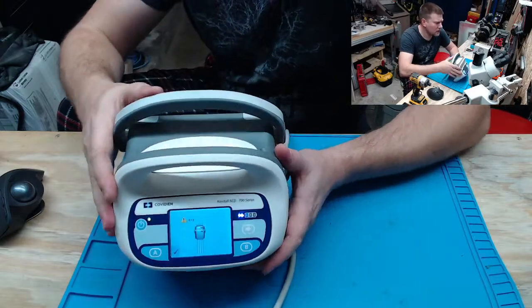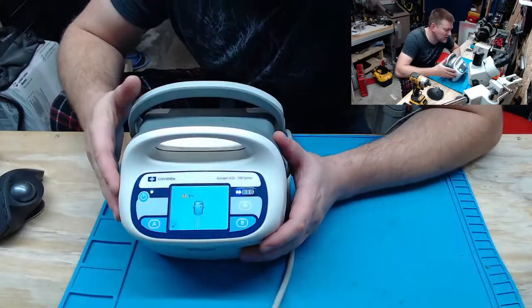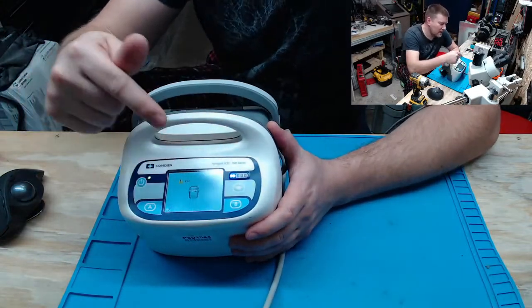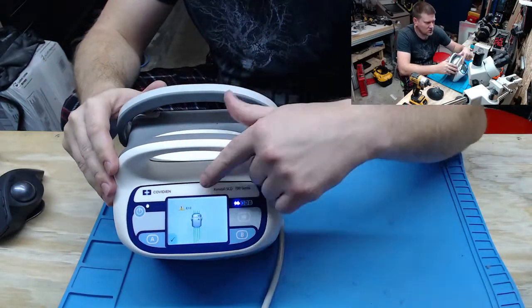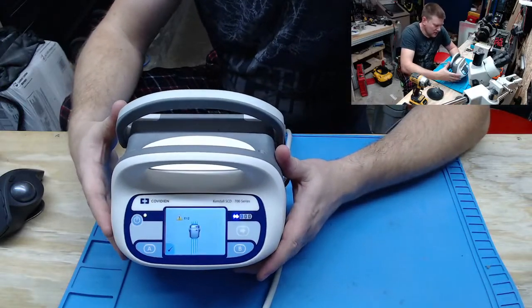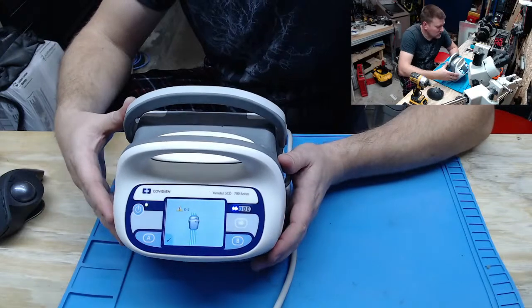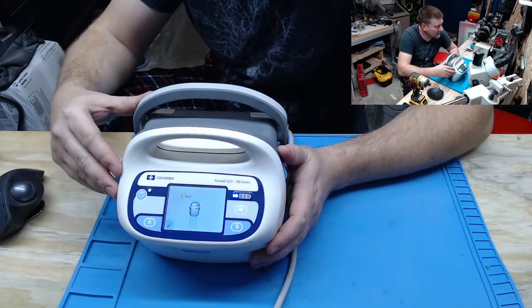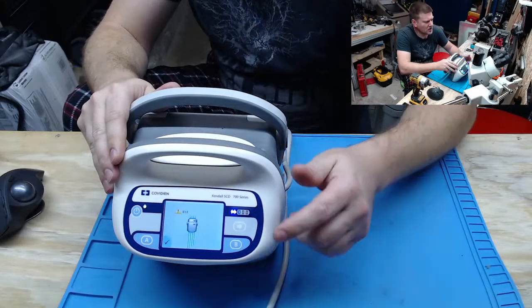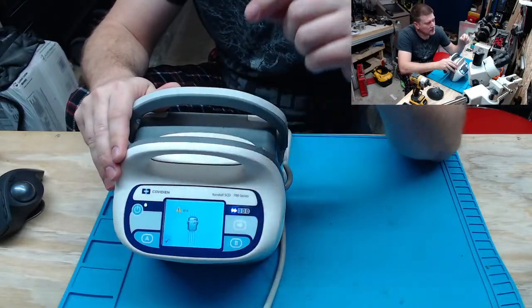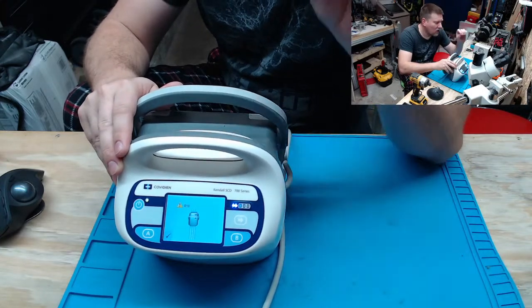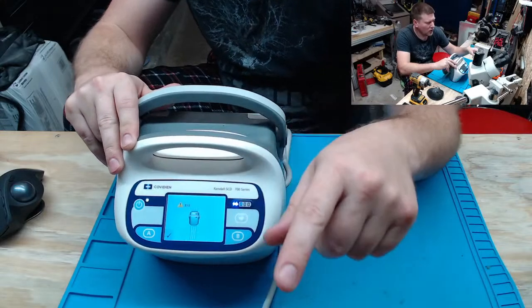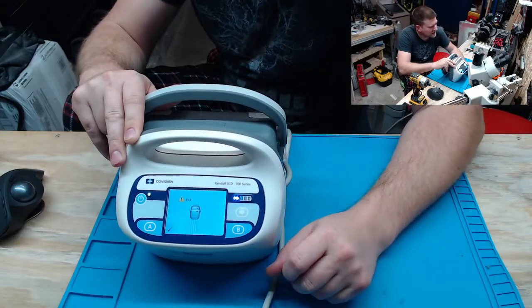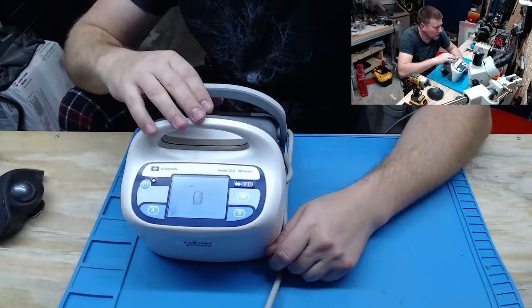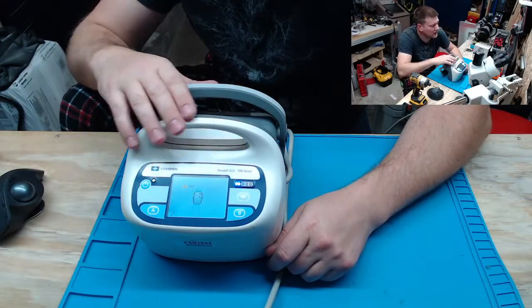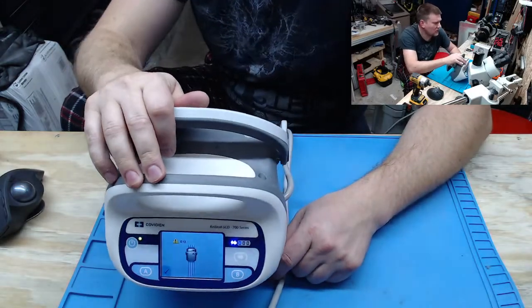Okay, so there's your first error code right there. It says, hey, what the hell, man? You got no sleeve connected to this guy. That is a very common problem, because as you see the connectors right there in the picture, very often they're damaged or not connected correctly, often damaged. You can see in the illustration where the hard plastic meets the soft tubing, these things break there all the time. Okay, there are tiny little hose barbs in the hard plastic, and because of the ripping on the hoses, bending them, pulling them, whatever, they snap off the little cheap plastic hose barbs.